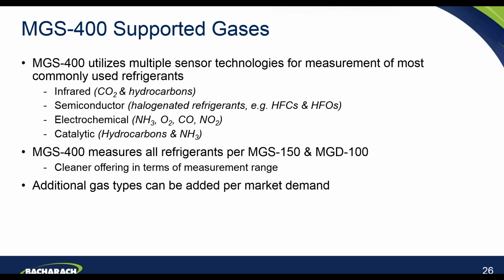In terms of supported gases, I mentioned earlier the investment in resource and capability that Bacharach has around supporting existing refrigerants in the market, but also offering detection solutions that can support new refrigerants as they come to the market. We support a number of different sensor technologies for measurements of the most commonly used ones today. So infrared typically for CO2 and hydrocarbons, semiconductor typically for those halogenated refrigerants, so your HFCs and HFO families, electrochemical sensors for particularly ammonia for this market, but we also do offer other versions for oxygen and CO, for example. And we offer catalytic-based sensor technologies for the higher ranges of hydrocarbons and ammonia. So when you're talking at the kind of lower flammability levels, that's the solution that we would utilize there.